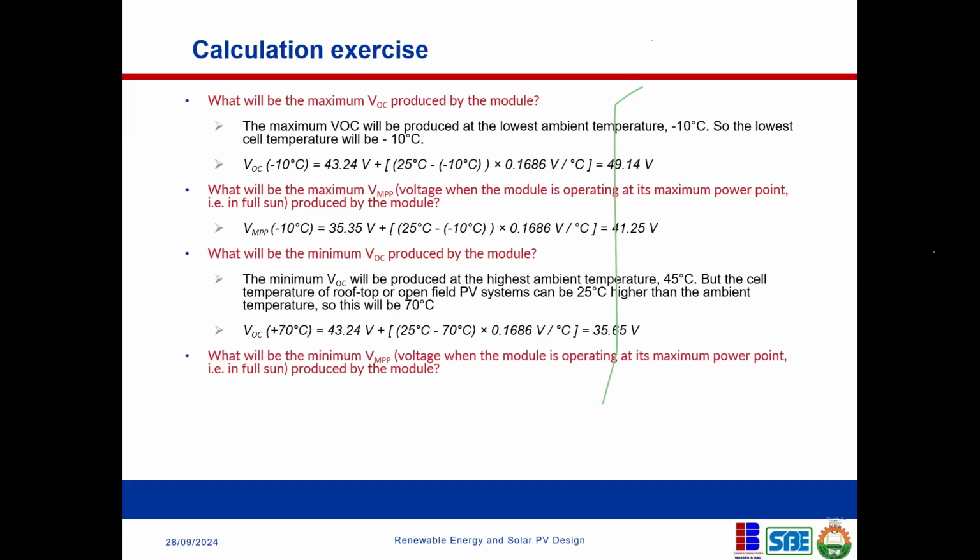Now, let's look at one of them. What will be the maximum open circuit voltage produced by the module? This is the characteristics of the module. The maximum open circuit voltage will be produced at the lowest ambient temperature. Now, the lowest ambient temperature is minus 10.